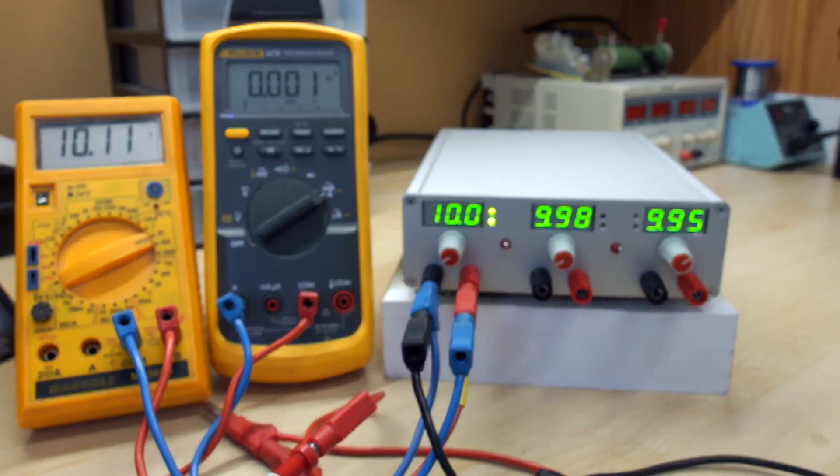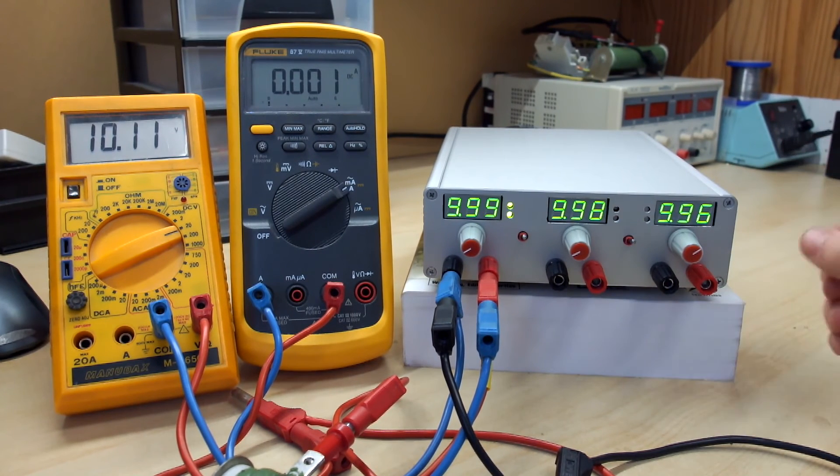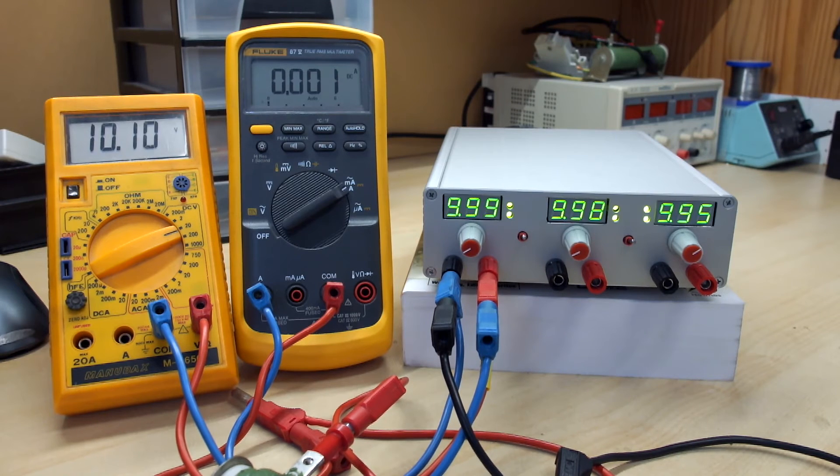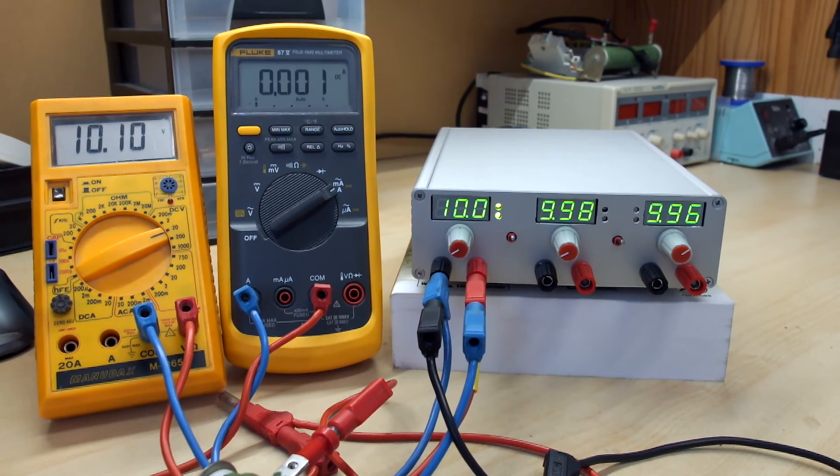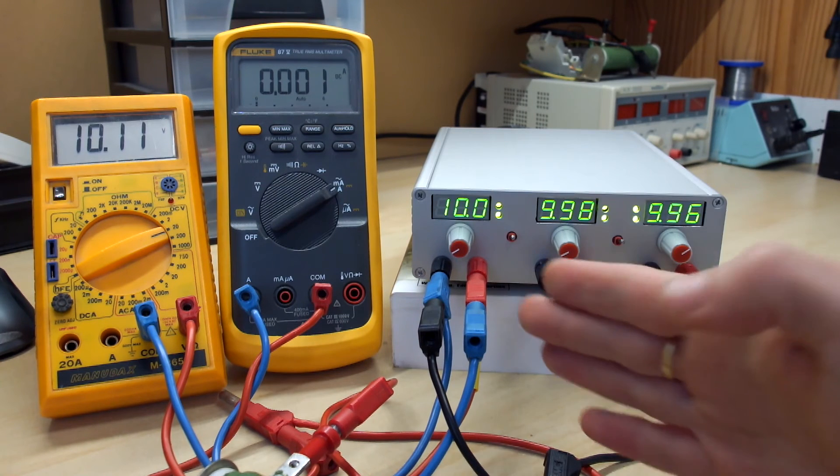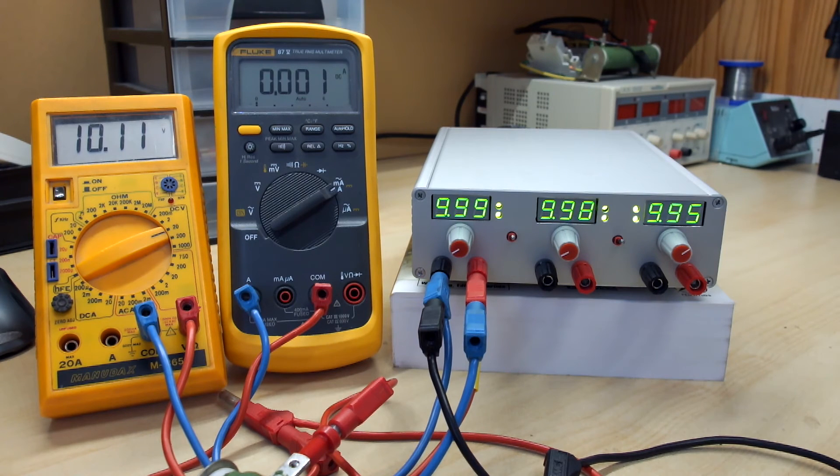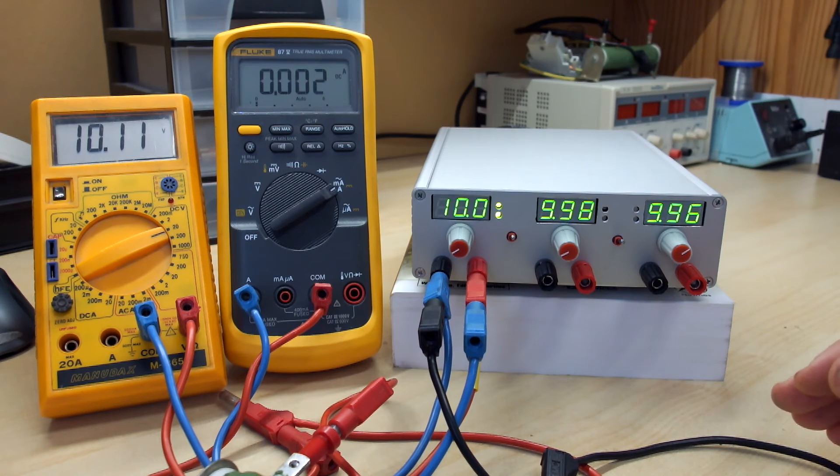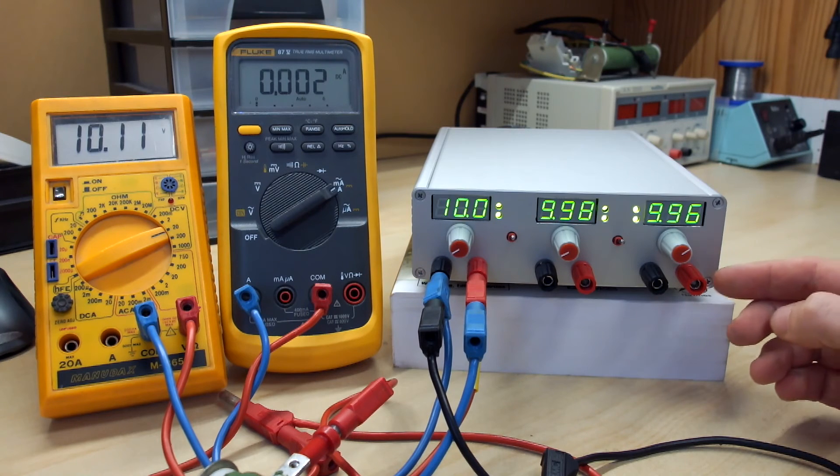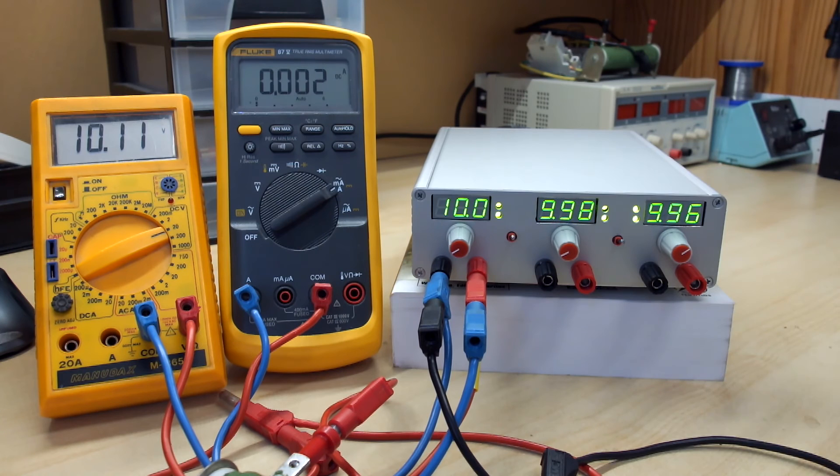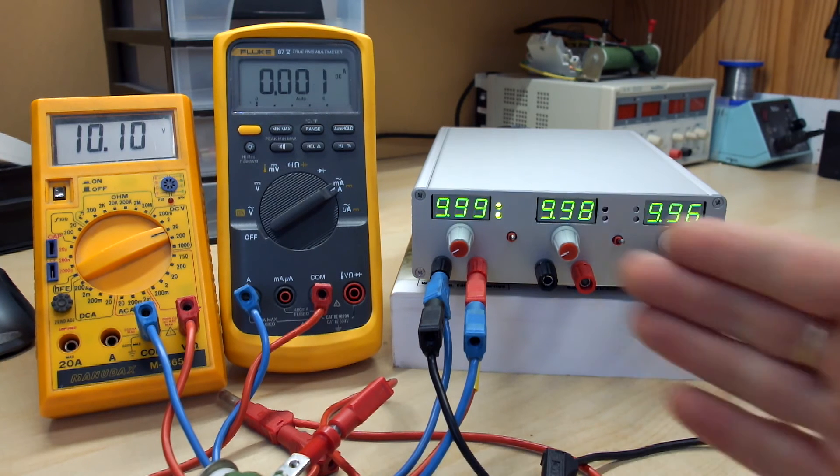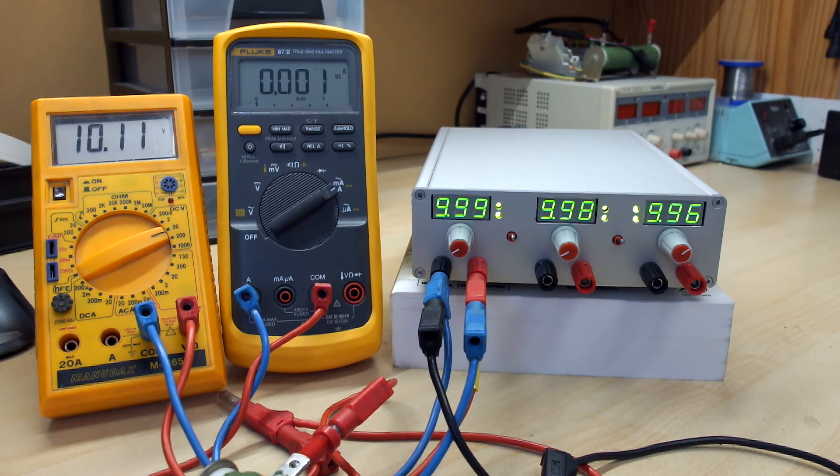I can set it for example to 10V. It is very important to have a functionality that allows a single adjustment of the output voltage in parallel mode. Because you need to have good current sharing and the output voltage must be strictly the same. So it is also important in tracking mode, when you have all outputs in parallel, or 2 outputs in parallel, to use a wire length the same between the output and your load. If you use 1 meter of wire between this output and your load, you need to do the same for all 3 outputs. The output resistance must be the same. So this ensures good current sharing between each channel. And it is the condition to get the maximum output current.